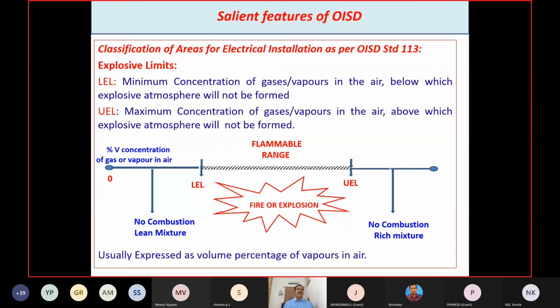Let us see the LEL. LEL is the minimum concentration of gases and vapors in the air, below which an explosive atmosphere will not be formed, and it will not get ignited even if you introduce any source of ignition. So here the concentration of gases and vapors will be less, and the oxygen percentage is high. About 21% of the air is oxygen. So the concentration of gas vapors is not adequate to form a flammable mixture. That is called a lean mixture.